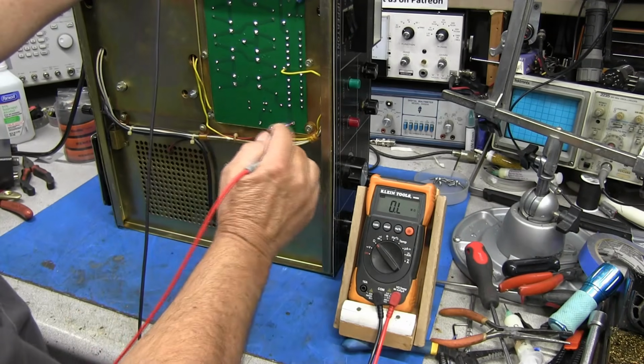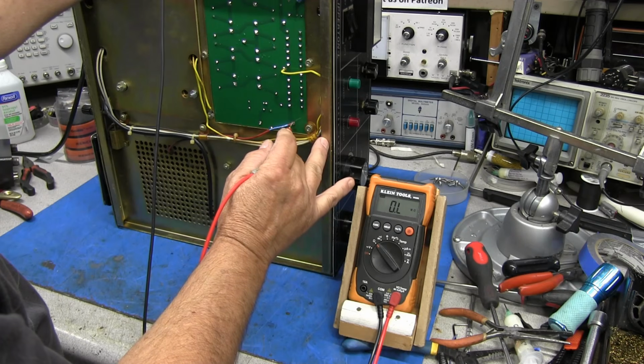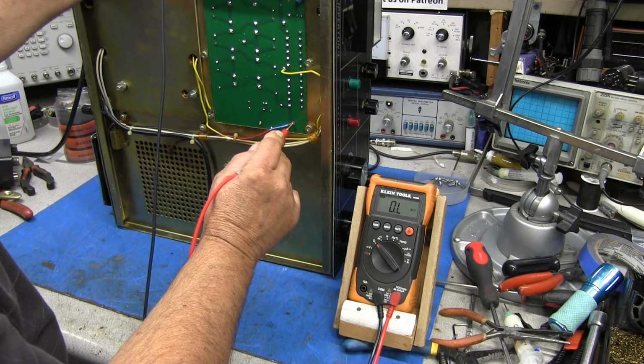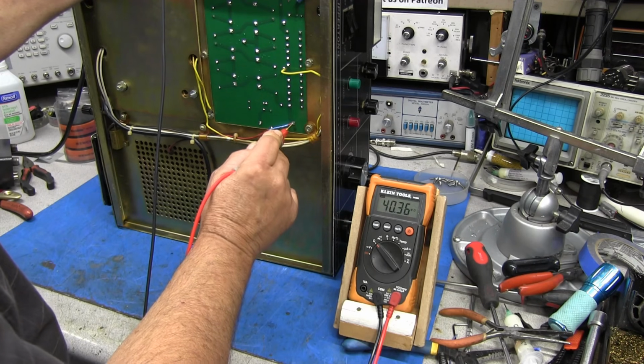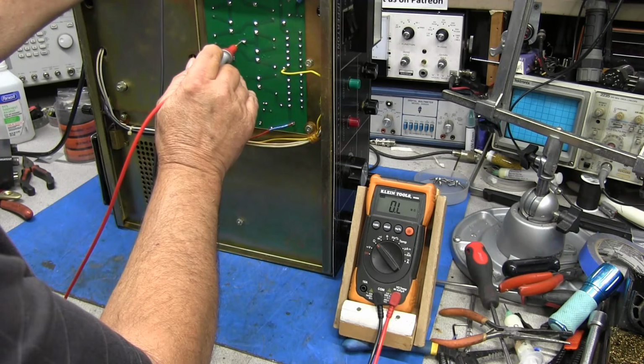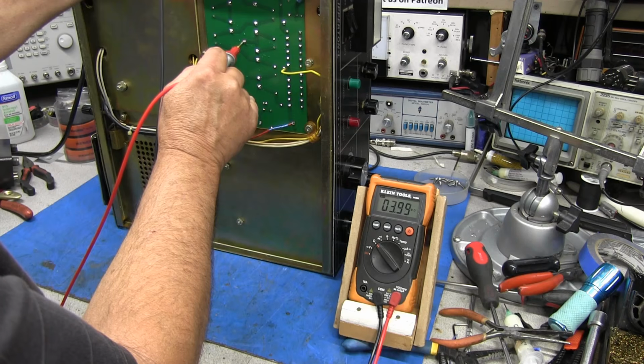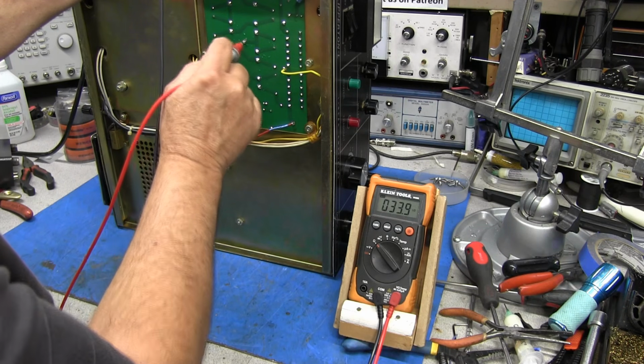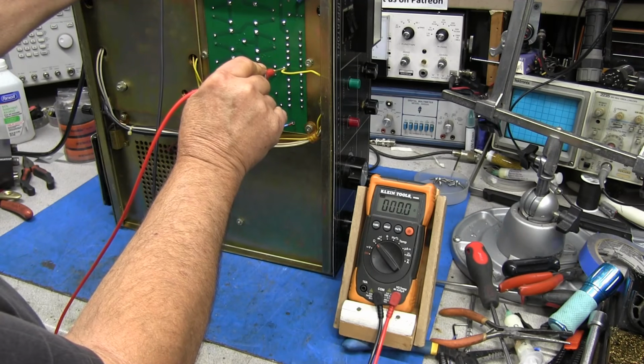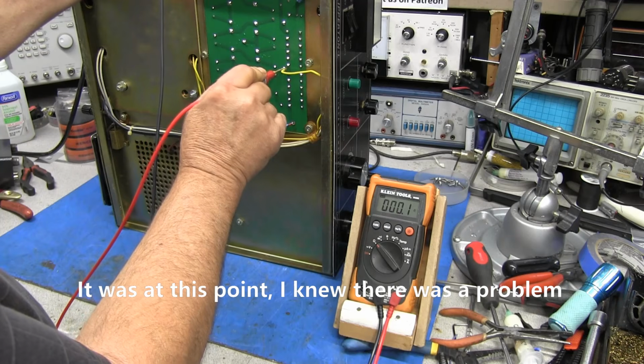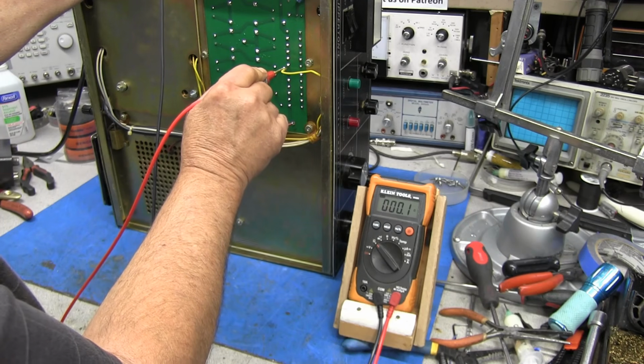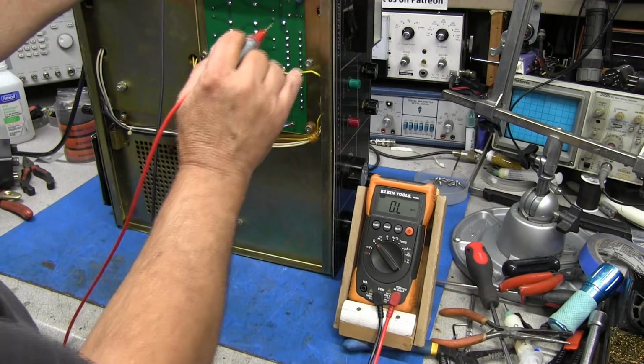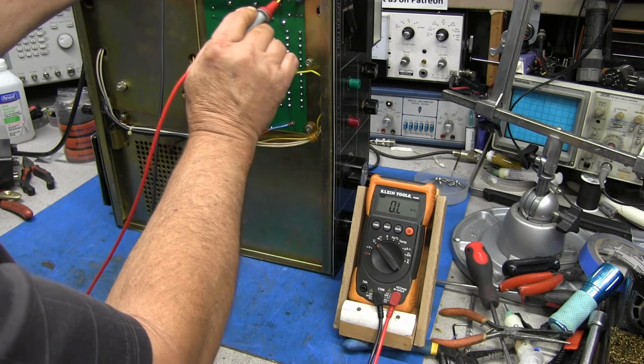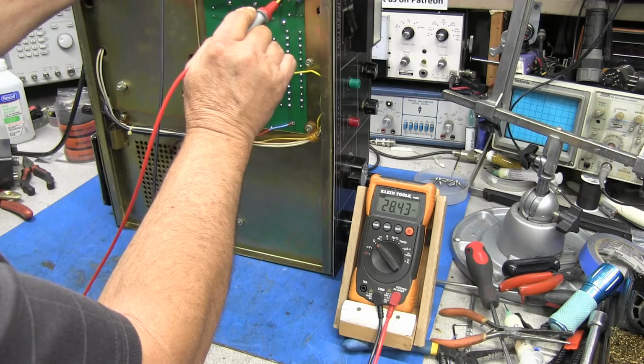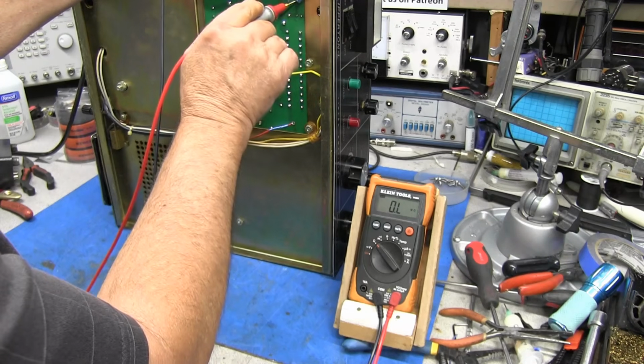What I'm going to do now is go to ground and check our B plus here, make sure there's no shorts to ground - we're way up in the mega ohms. We'll go from transformer 2 to ground, and we've got a good high reading there. Go from transformer 1 to ground, then to our low voltage AC to ground. That looks good. Low voltage DC won't really matter.